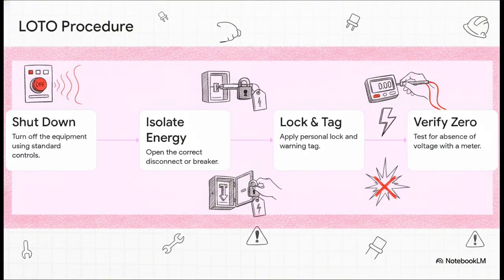This requires a strictly structured, non-negotiable process. First, you shut down the machine normally using its standard controls. Second, you isolate the energy by opening the correct disconnect or breaker. Third, you apply your personal lock and tag to that disconnect. And fourth, and honestly this is probably the most critical step of the whole thing, you must verify that the energy is actually gone. You try to turn the machine on to ensure it doesn't start, and then you use a properly rated meter to test the conductors.